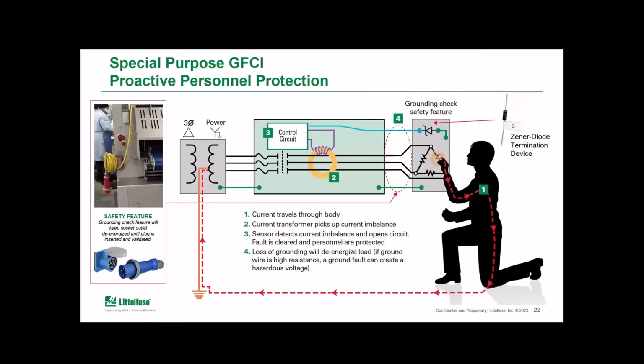So just to quickly outline the operation of the special purpose GFCI, the three-phase device at 480 volts really operates on similar principles as a single-phase GFCI in your bathroom, except that it has a 20 milliamp pickup. So if a person makes contact with an energized part of that circuit, it allows current to flow through their body to ground, and the built-in current sensor can see that current returning to the power source outside of the power cables and react to it.